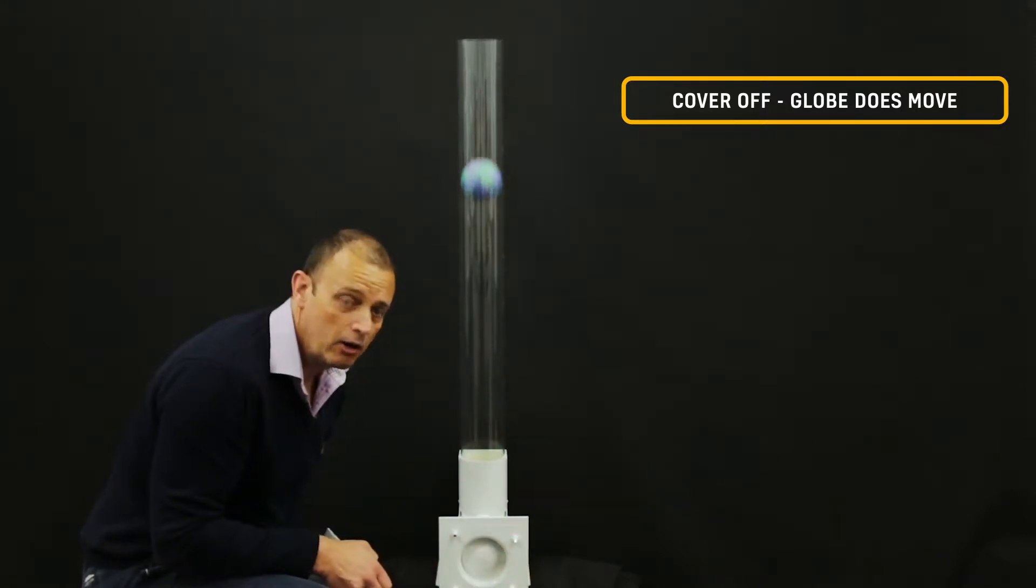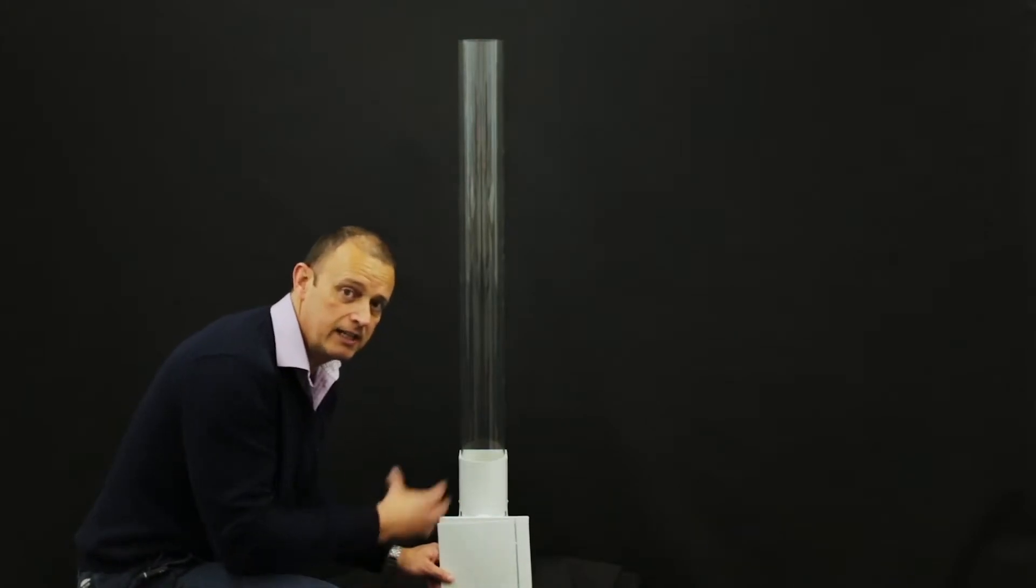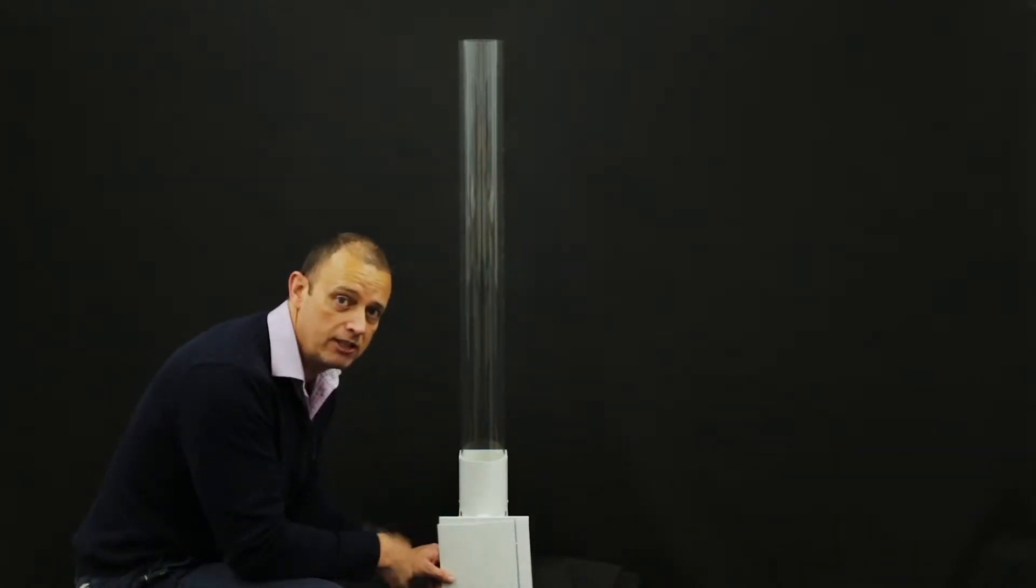Just by having this front cover on, you'll see it doesn't move the globe. But if I gently just move that away, the globe moves. So that's just showing you if you've got a fan that's on a ducted system, although it looks nice, it's not coping with that extra resistance.